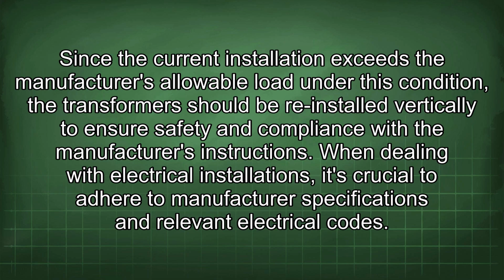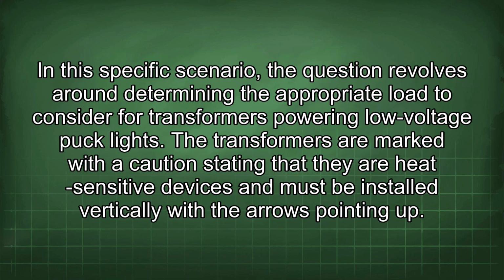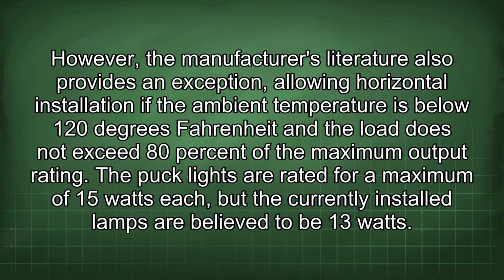When dealing with electrical installations, it's crucial to adhere to manufacturer specifications and relevant electrical codes. In this specific scenario, the question revolves around determining the appropriate load to consider for transformers powering low voltage puck lights. The transformers are marked with a caution stating that they are heat-sensitive devices and must be installed vertically with the arrows pointing up. However, the manufacturer's literature also provides an exception, allowing horizontal installation if the ambient temperature is below 120 degrees Fahrenheit and the load does not exceed 80% of the maximum output rating.